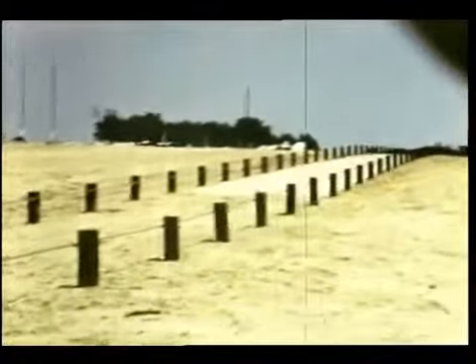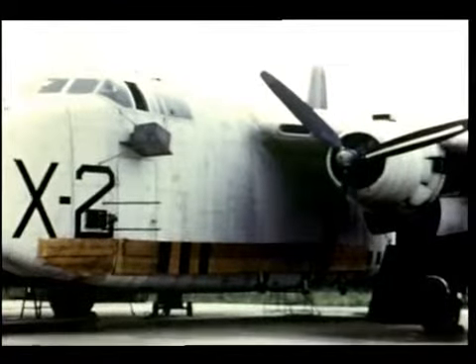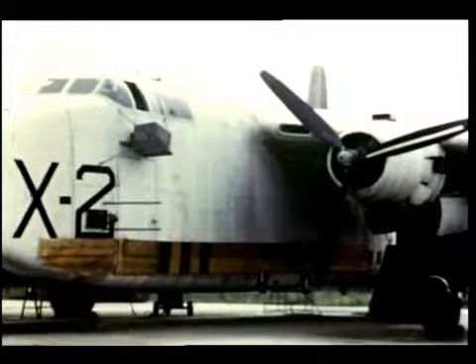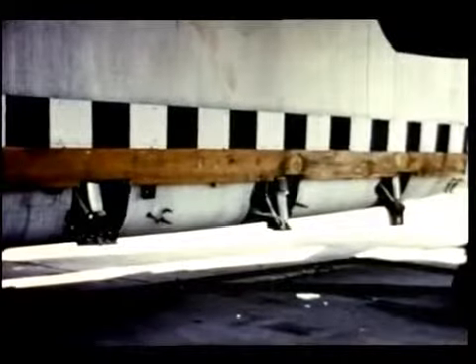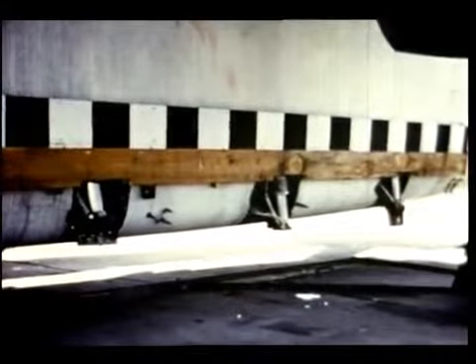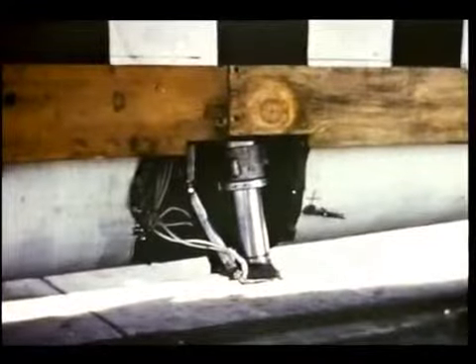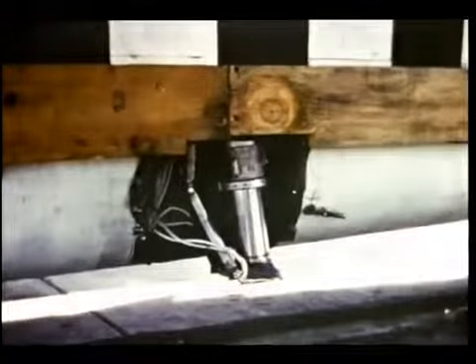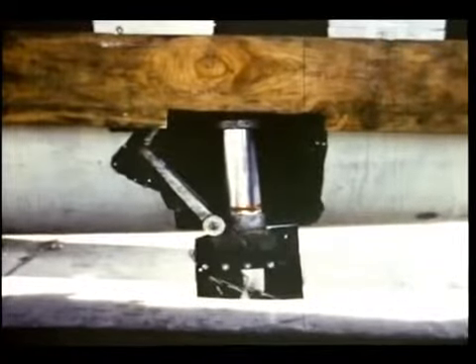In order to study this type of ignition, a concrete strip was built along the slide path of the crashed airplane. Selected samples of airplane metals were fastened to protruding ends of pneumatic wheel struts salvaged from airplanes crashed in this study. Upon crash, these metal samples bear on the concrete strip with a contact force great enough to produce sparks of sufficient size and temperature to ignite aviation-grade gasoline. Sparks from this portion of a steel propeller blade and this steel wheel strut produced fires. Abraded particles of this portion of an aluminum propeller blade did not produce ignition.